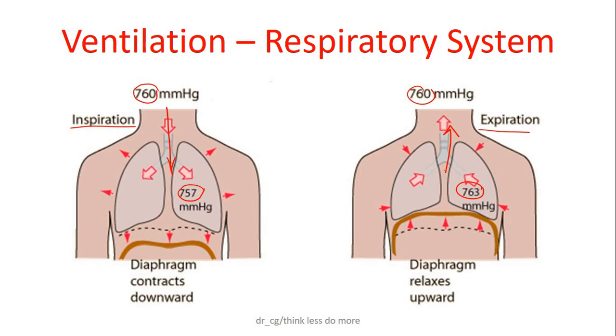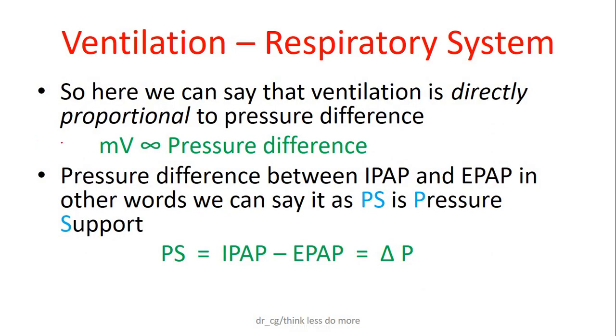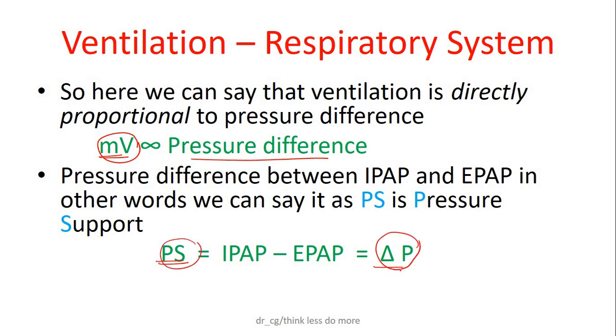So from this, we can say ventilation is directly proportional to the pressure difference — what we call in medical terminology pressure support. So MV (minute ventilation) is directly proportional to PS (pressure support), or delta P, which is the difference between your IPAP and EPAP.